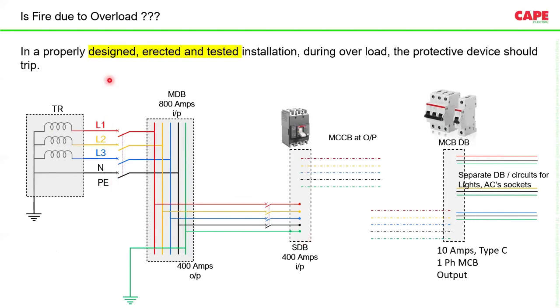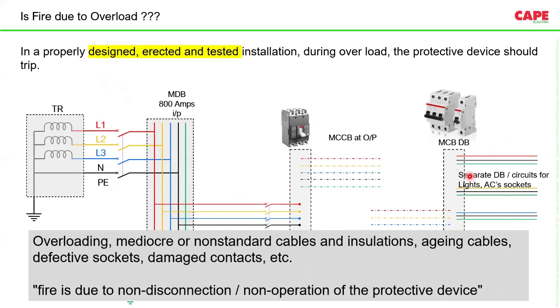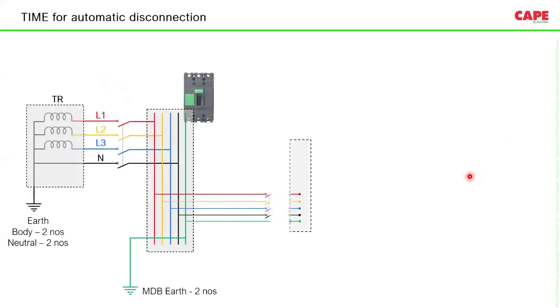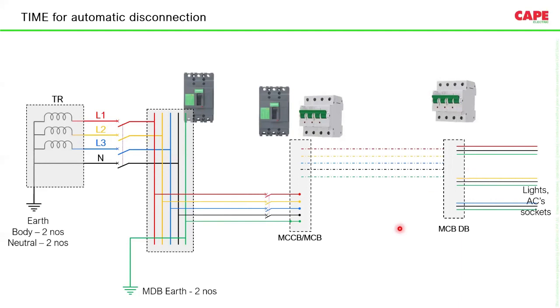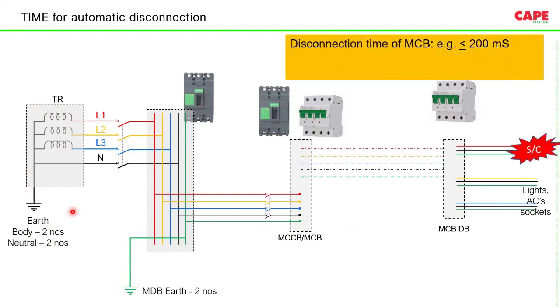Now, please note that in a properly designed, erected, and tested electrical installation, overload and short circuit shall not create any incident, because these protective devices are supposed to disconnect, provided they are not only selected and installed properly, but also tested properly. Most often, this testing, especially fault testing, of the disconnection of the protective device during an earth fault very rarely happens because we use a kind of TT system. TT system in the sense the transformer neutral is connected to two earth pits and the panel board earth bus bar is connected to a separate earth pit. As a result, it becomes a TT system, but sometimes underground these are also connected. Then it becomes an inefficient TN-C-S system, which is very dangerous. Disconnection within the recommended time of 200 milliseconds may not happen.